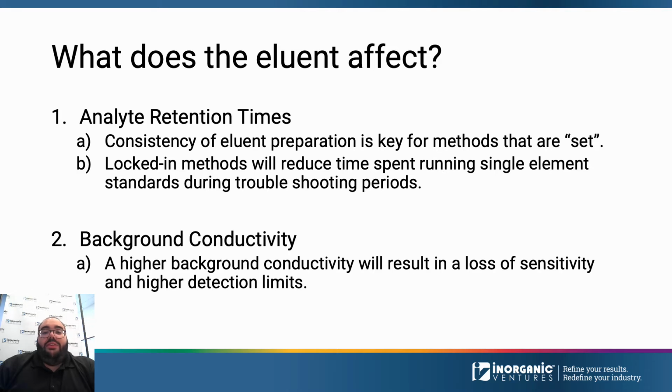The eluent also controls the background conductivity of the instrument. Again, the higher the concentration of the eluent, the higher the background conductivity. We will show examples of how high background conductivity can impact instrument sensitivity and detection limits.